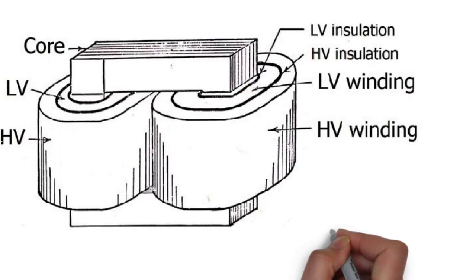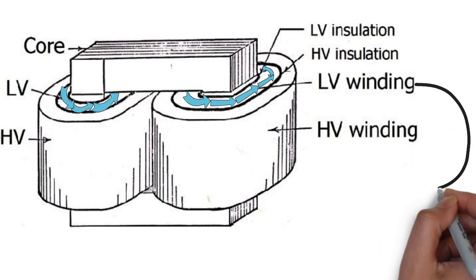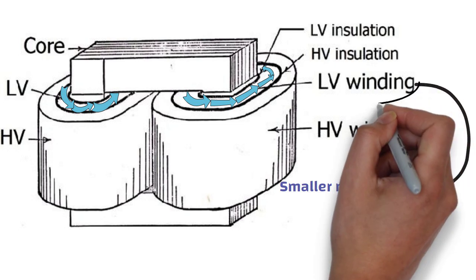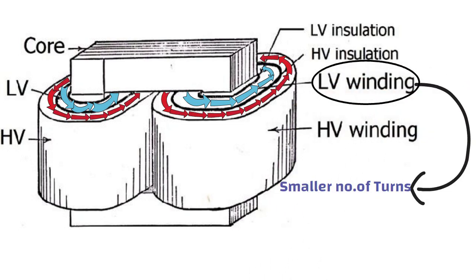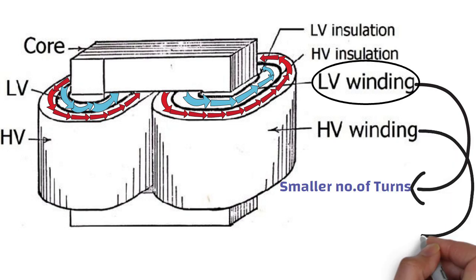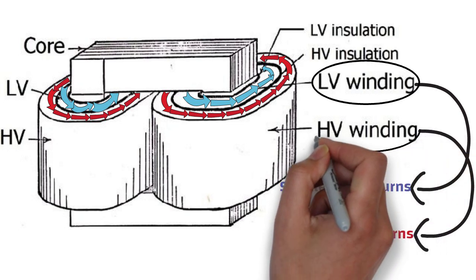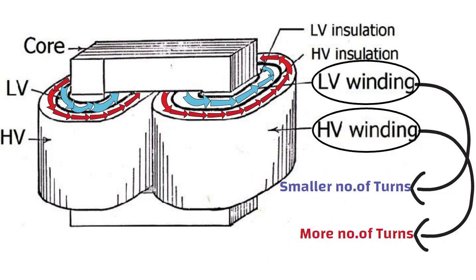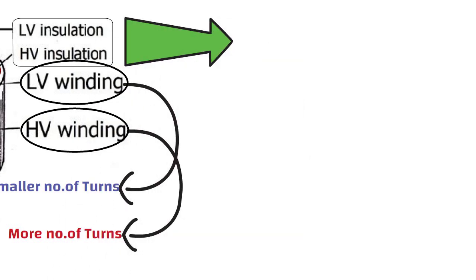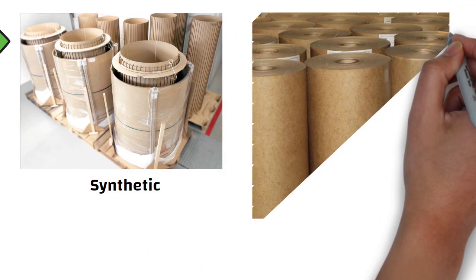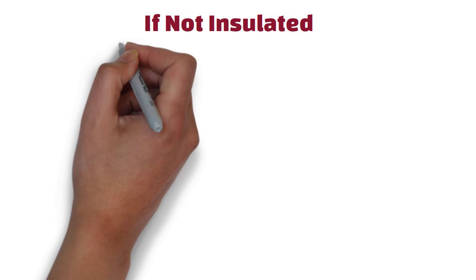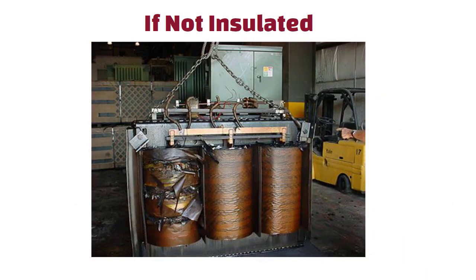Now let us understand how this winding is done in a transformer. The winding which is close to the core has a smaller number of turns. It is called the low voltage winding. And the winding which is placed on the low voltage winding has more turns. It is called the high voltage winding. Please note, the core, low voltage winding and high voltage winding are separated by insulation. This insulation material can be synthetic materials, paper or cotton, etc. If we don't keep this insulation material, then it can cause severe damage to the transformer.